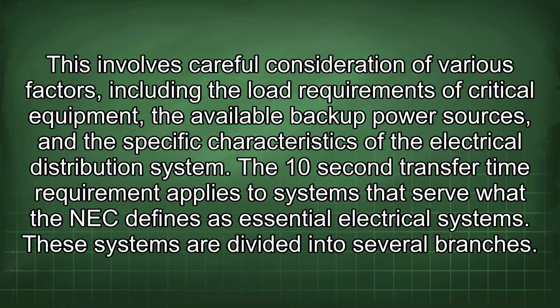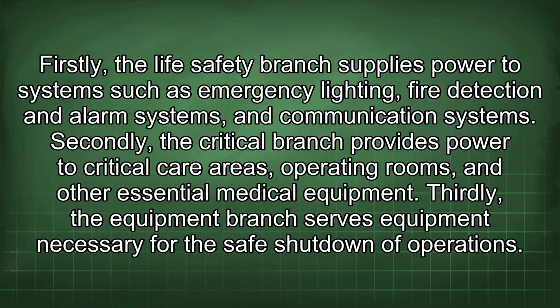The 10-second transfer time requirement applies to systems that serve what the NEC defines as essential electrical systems. These systems are divided into several branches. Firstly, the life safety branch supplies power to systems such as emergency lighting, fire detection and alarm systems, and communication systems. Secondly, the critical branch provides power to critical care areas, operating rooms, and other essential medical equipment. Thirdly, the equipment branch supplies equipment necessary for the safe shutdown of operations.